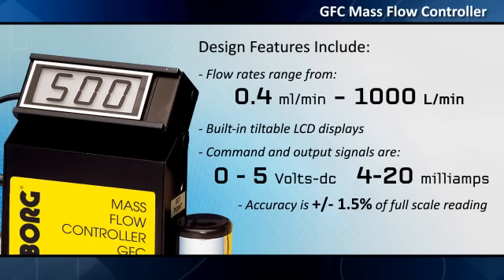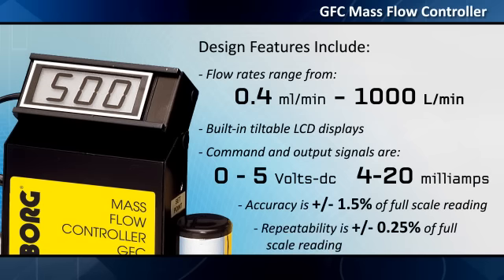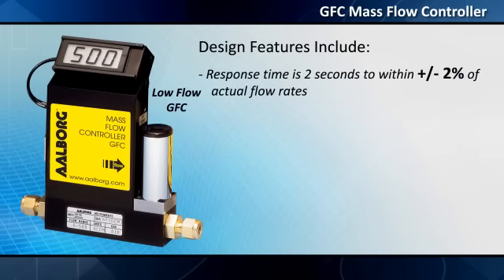Accuracy is plus or minus 1.5% of full-scale reading. Repeatability is plus or minus 0.25% of full-scale reading. Response time is 2 seconds to within plus or minus 2% of actual flow rates, and time constant is 800 milliseconds.